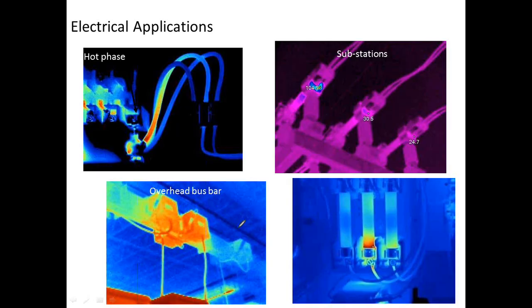In electrical applications, looking at various pieces of equipment, the infrared camera is looking at emitted radiation. In circuits where we have a loose connection, for example, there's elevated temperature on the wire, which we can compare with another wire to give ourselves a delta of understanding what's going on. Again, a connection issue here, and at this substation we can see a significant change of temperature due to some kind of connection problem.